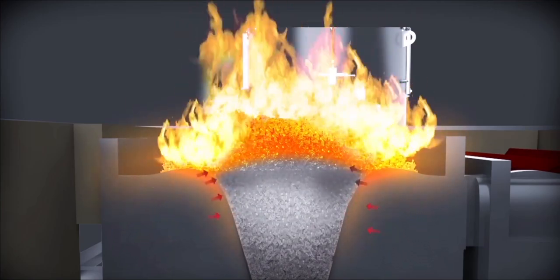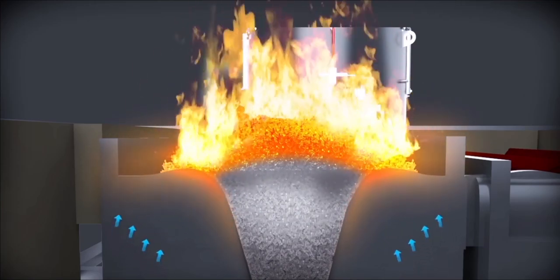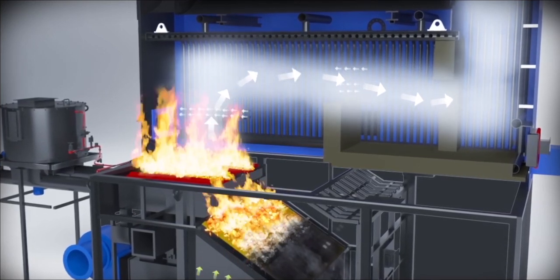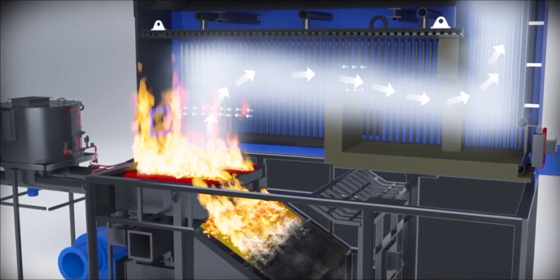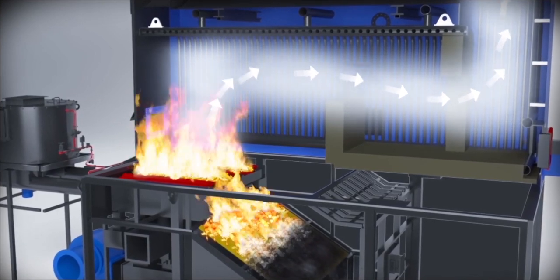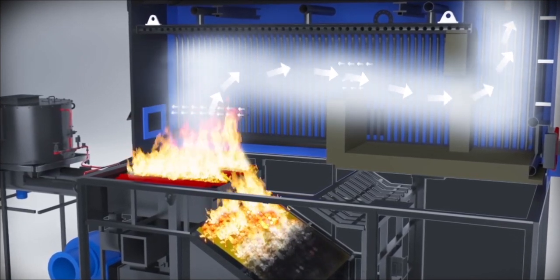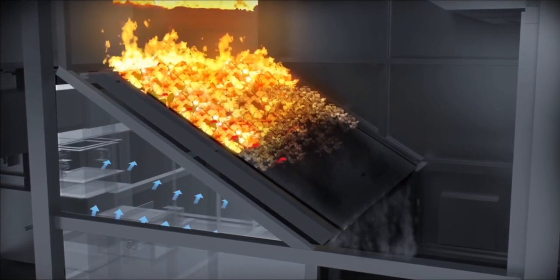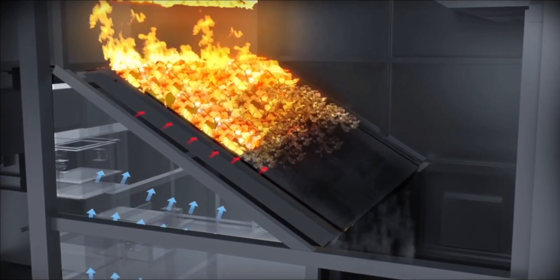The air penetrates the heap of fuel through the nozzles provided on the castings. Once the fuel is lighted up, gasification of fuel on the top layer of the heap facilitates volatile release and its subsequent combustion. The balanced combustion of fixed carbon or char happens on flat surfaces in the furnace or in sloped stationary grate bars, with some air also supplied for char combustion in the stationary grate section.